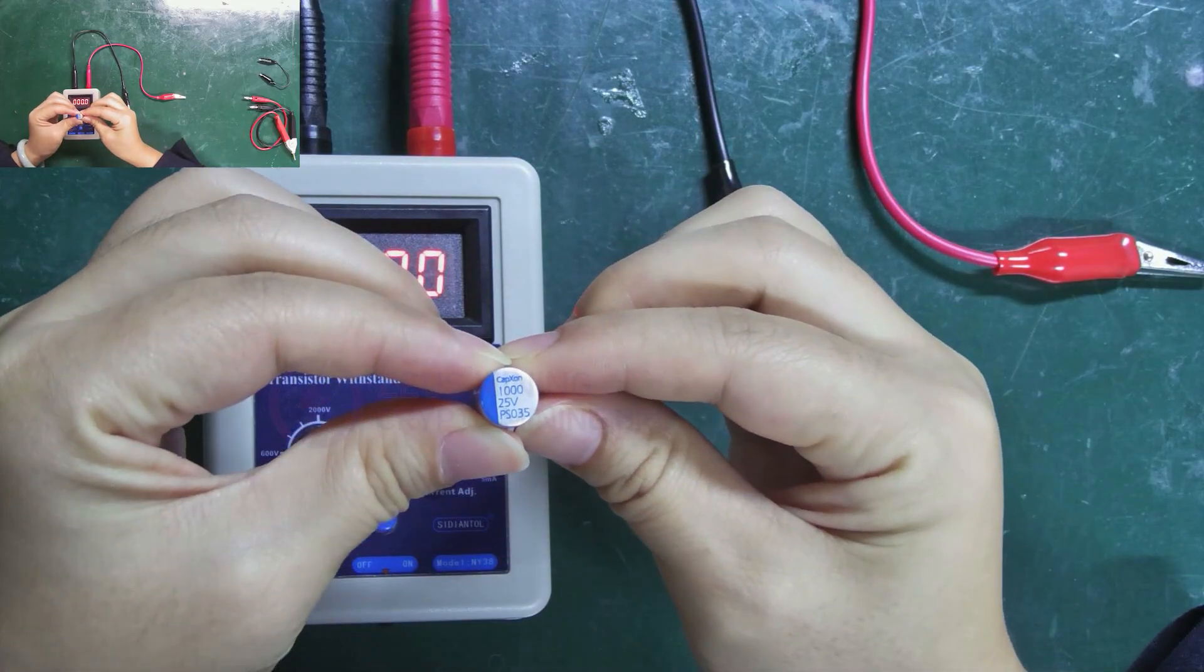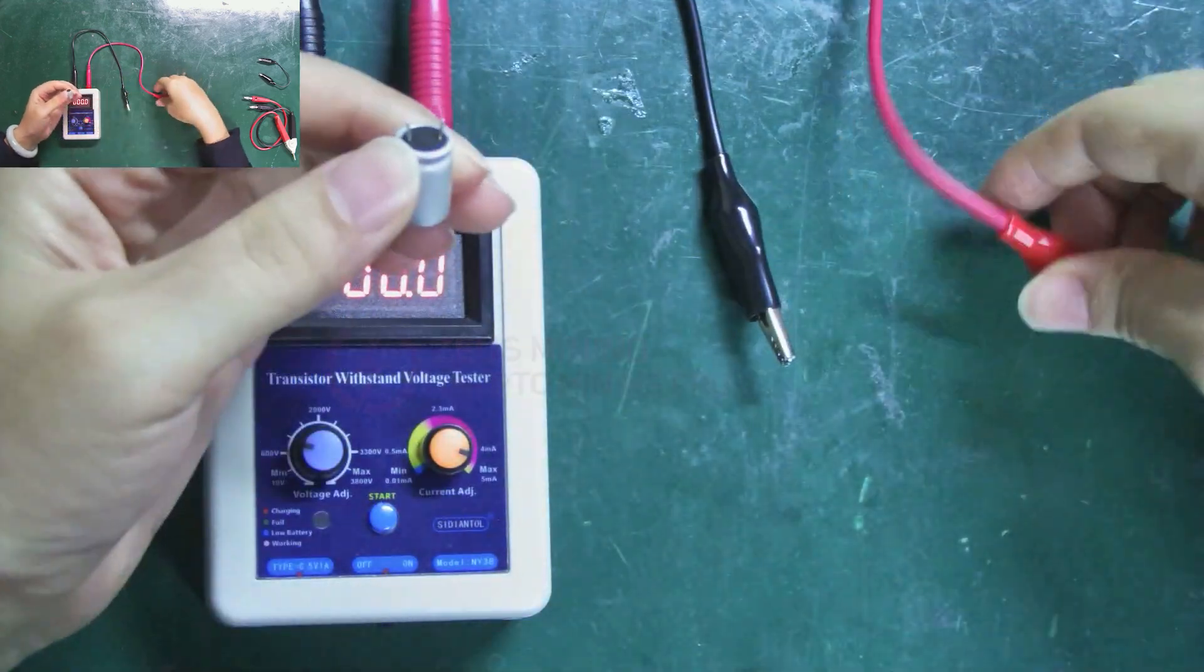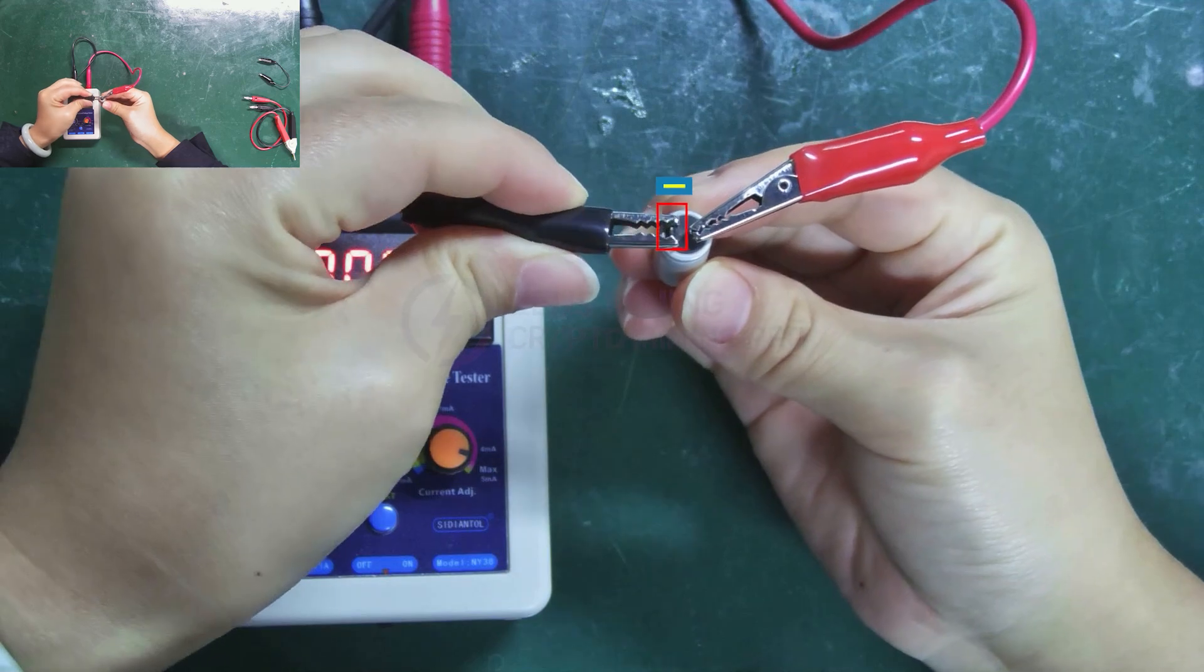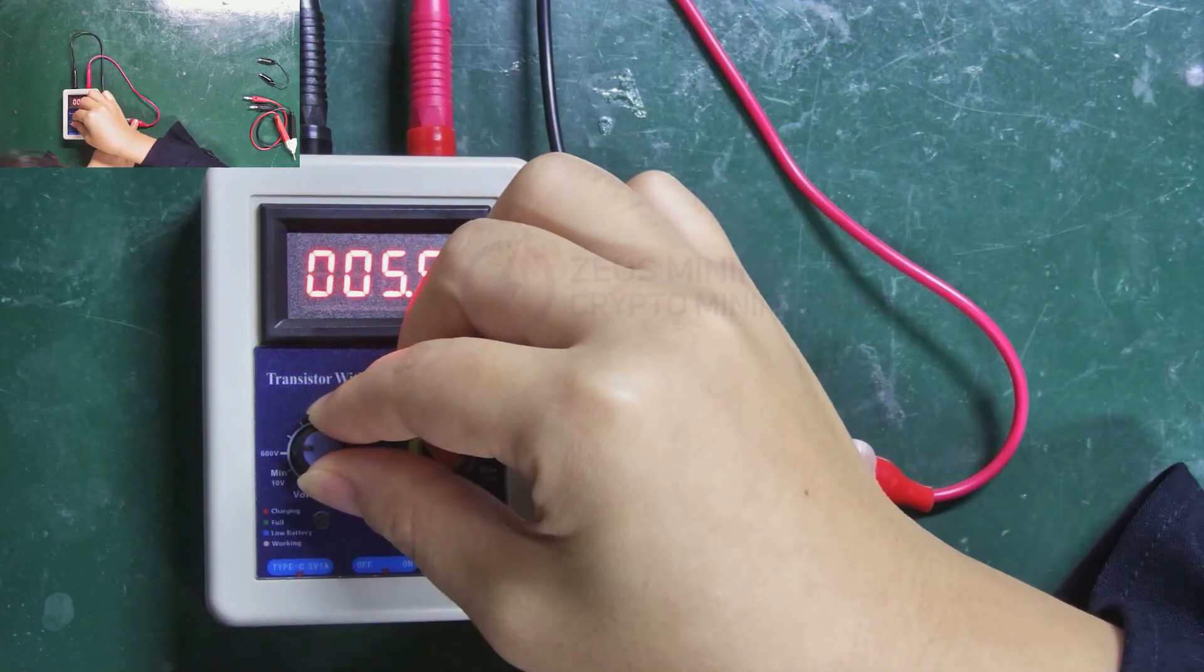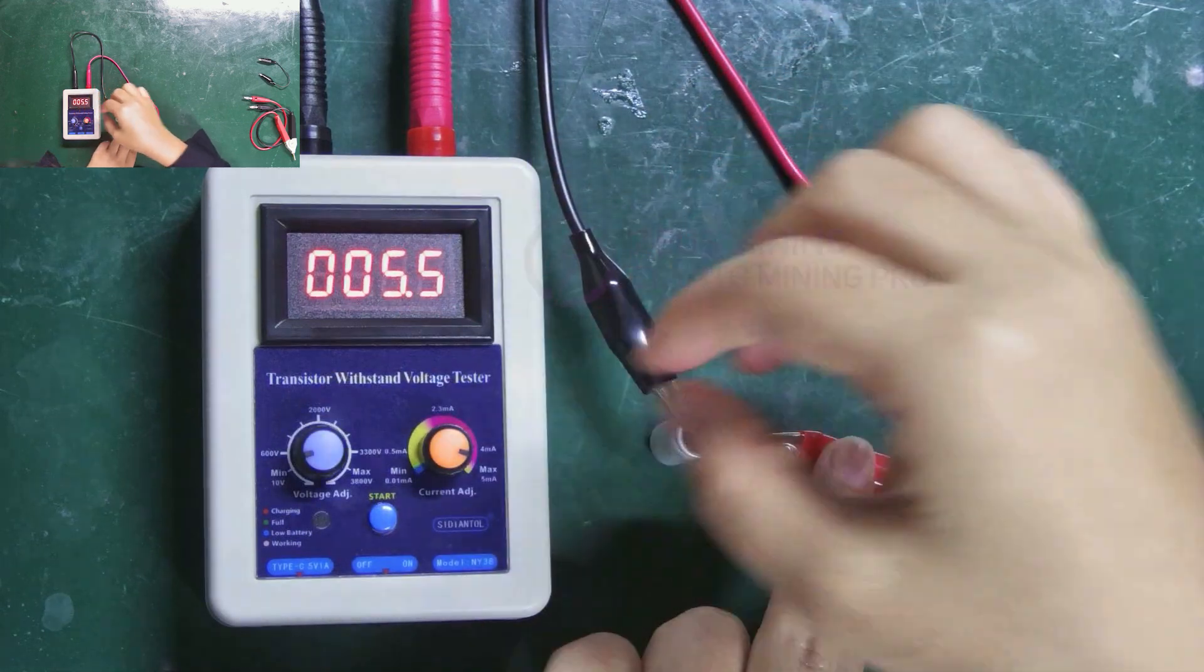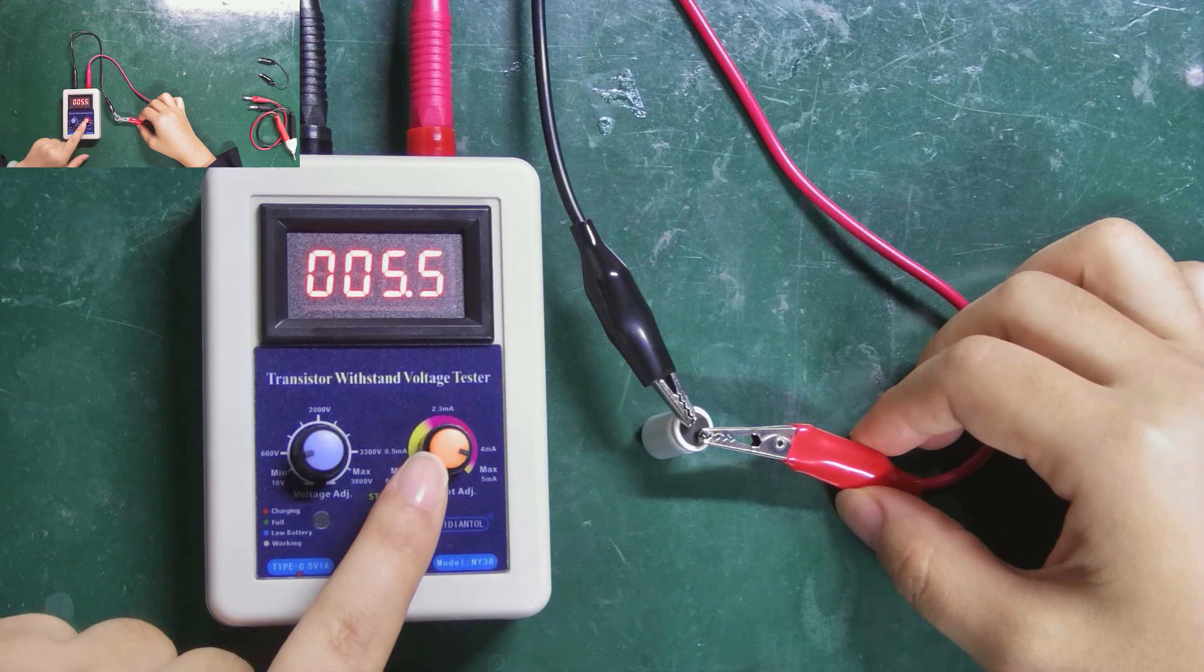Next, let's measure the 25 volts small capacitor. Likewise, connect the red clip to the positive pole and the black one to the negative. Adjust the voltage to be 1.5 times greater than the component's withstand voltage value. The current can still be set to maximum. No further adjustment is needed.